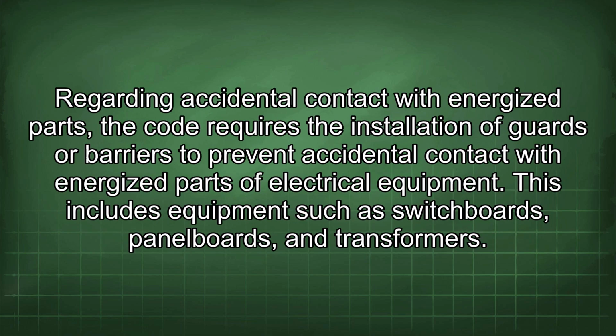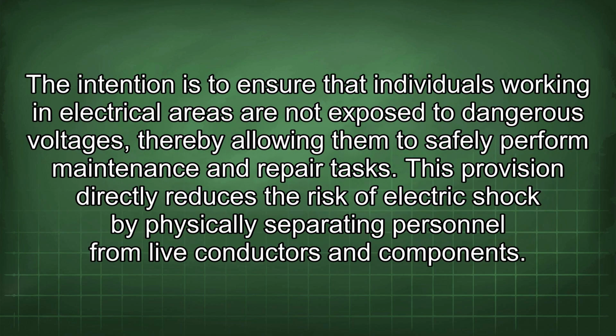Regarding accidental contact with energized parts, the code requires the installation of guards or barriers to prevent accidental contact with energized parts of electrical equipment. This includes equipment such as switchboards, panel boards, and transformers. The intention is to ensure that individuals working in electrical areas are not exposed to dangerous voltages, thereby allowing them to safely perform maintenance and repair tasks. This provision directly reduces the risk of electric shock by physically separating personnel from live conductors and components.